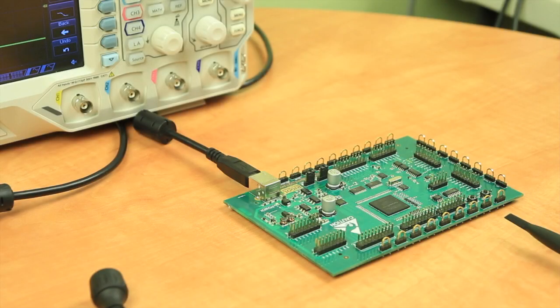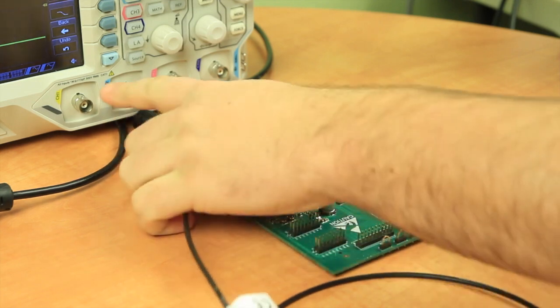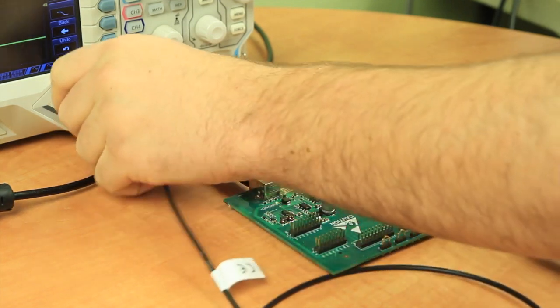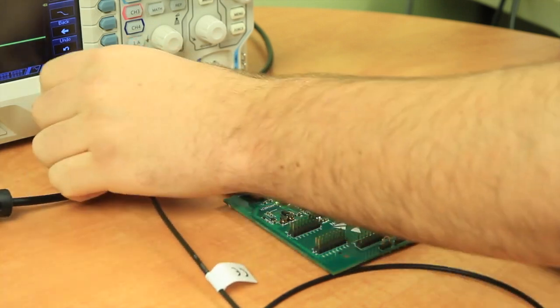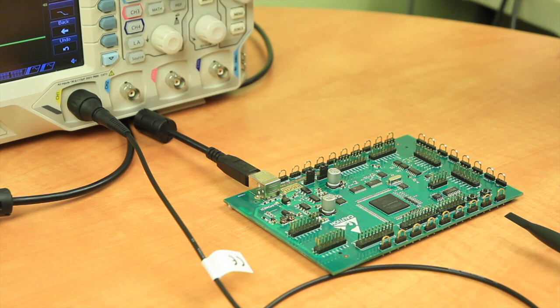To demonstrate how to do some probing around with the probe itself, to start off, I'm going to connect our probe by pushing on the slot in the scope itself. There's two pins on here, so you have to line it up before rotating on. So once you push it in, you then rotate it, and the probe is then attached.